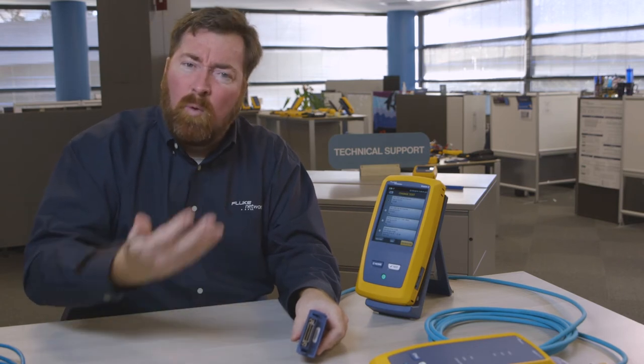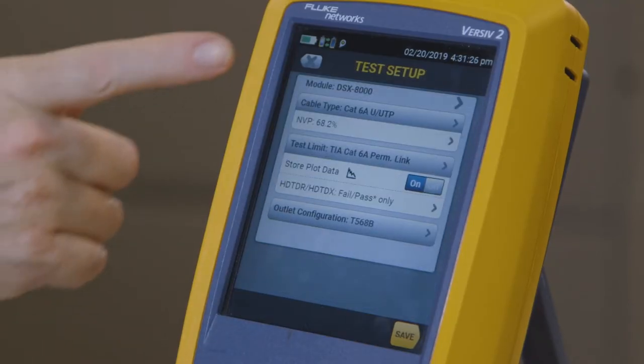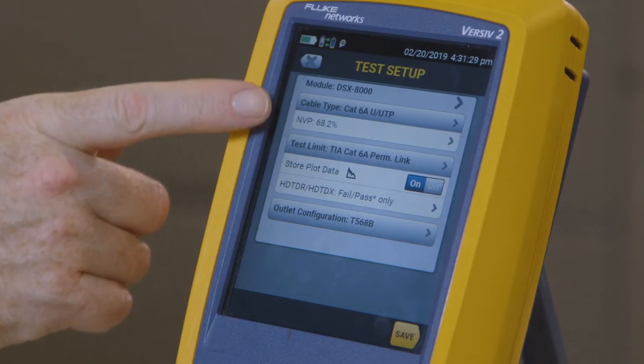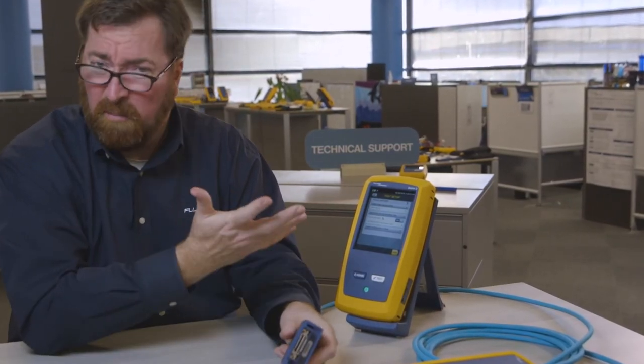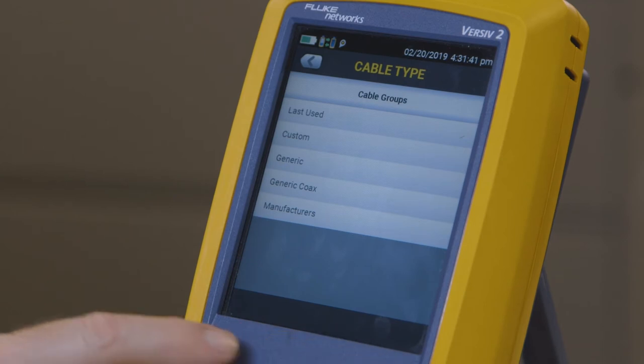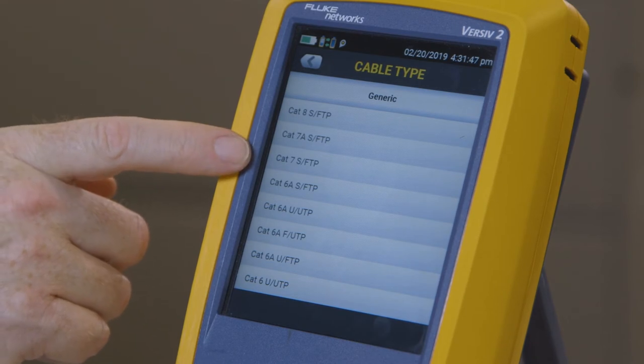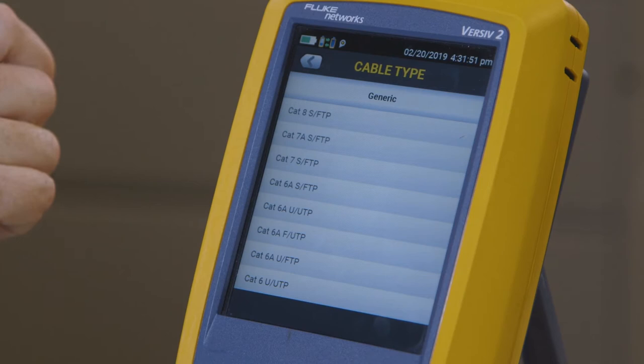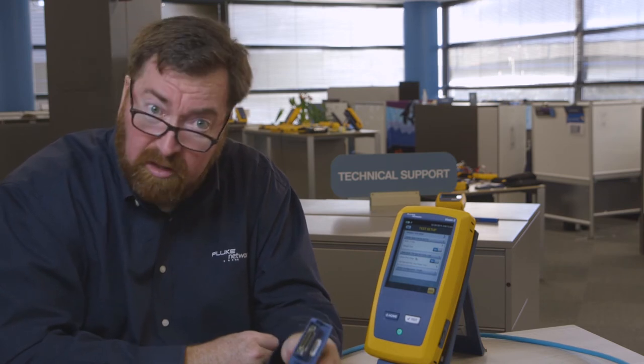It's not as well known as it could be, so let me explain it. When we go in here and choose to do a new test, we default to standard Category 6A unshielded cable and standard Category 6A permanent link. If I select the cable type and go down to more, then select generic, I can select Category 7 or Category 7A. SFTP suggests there's both an individual and an overall shield on the cable. The shield test will determine pass or fail — we check for continuity in the shield and make sure it follows the path of the cable.